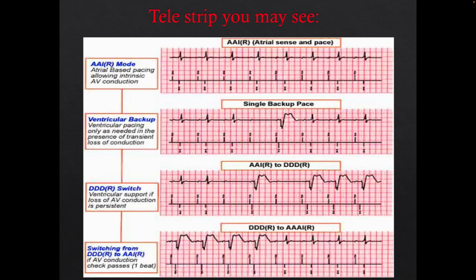This one is probably the biggest telemetry nightmare that we get calls about constantly. Because doesn't that look like there was either a sensing issue or a capture issue there, right? Because there's no beat after this nice P wave. Well, in these lovely devices, both defibrillators and pacemakers, there is a mode. So remember I said we don't like RV pacing if they don't have resynchronization, because it could cause more heart failure, decrease cardiac output, cause more hospitalizations for heart failure. There's something called AAI to DDD or VVI mode, meaning that the device can naturally switch back and forth as it needs to between these.